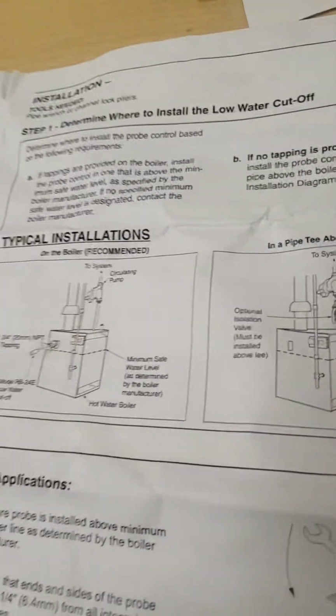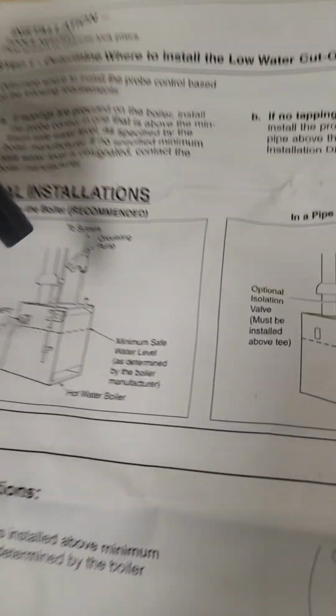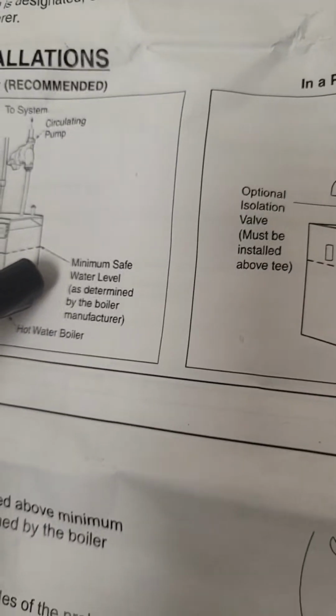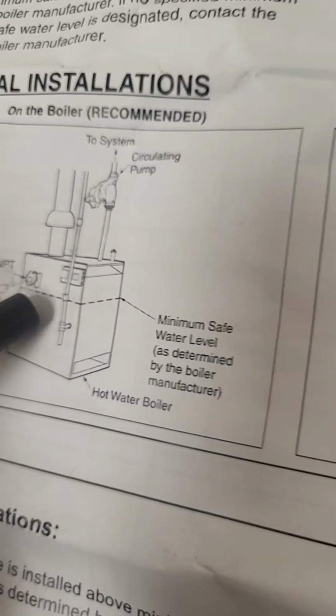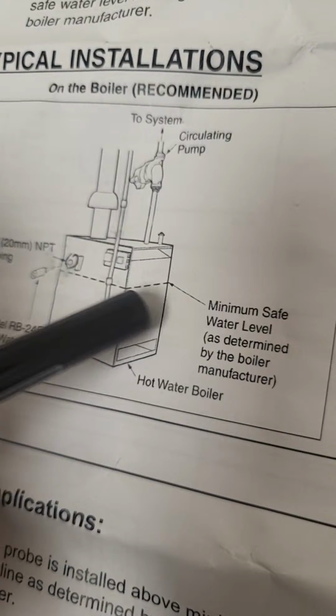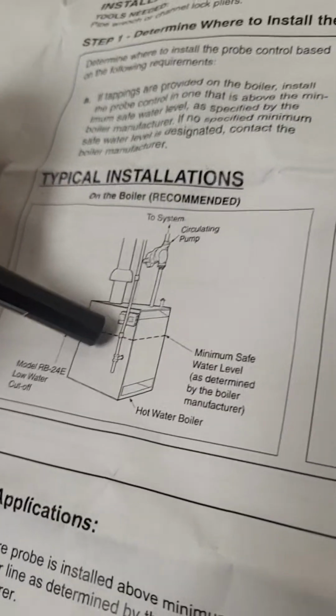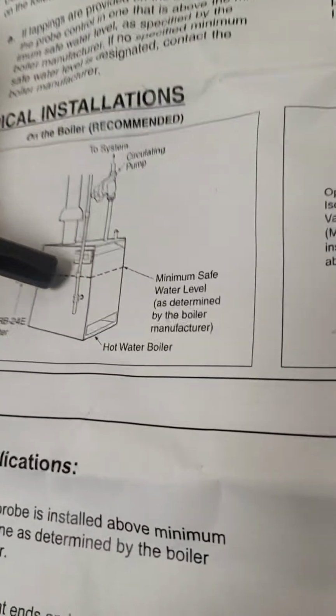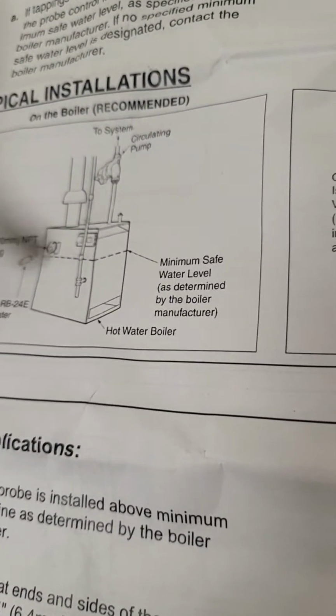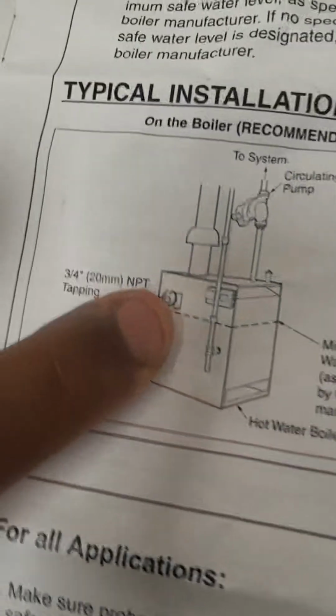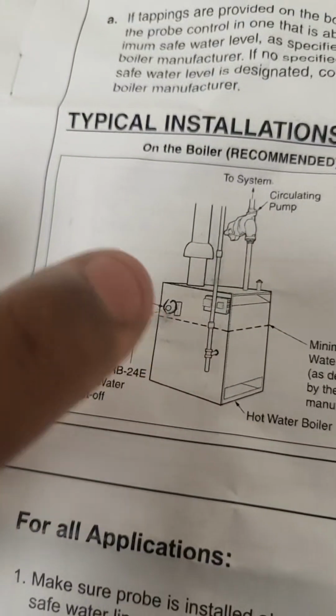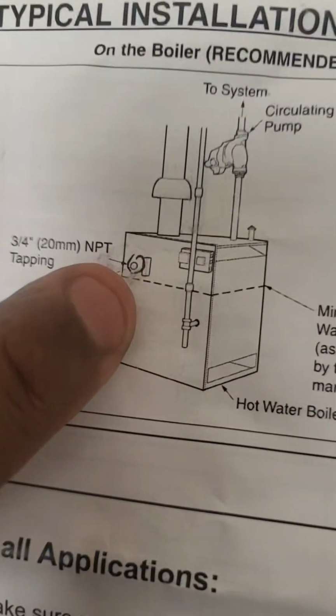Moving on, because I feel like I'm talking in circles. This low water cutoff has a minimum safety level, usually 3/4 up, similar to a hot water or steam boiler. But always resort to your manufacturer specifications, it'll tell you exactly how high up to install this. Essentially you want the low water cutoff, and once again this is a hot water gas boiler.